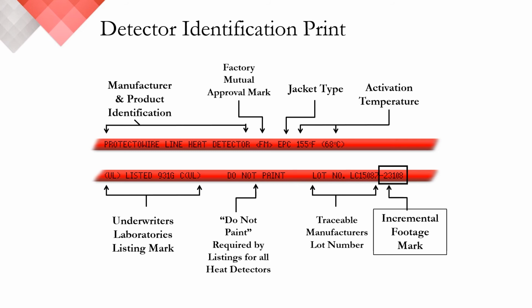So we recommend recording the length of each zone during the initial commissioning process, as that can be very helpful later when troubleshooting. Further, certain Protectowire control equipment is available with an alarm point location meter. This meter will help you determine where the detector is shorted. The short can then be easily located using the incremental distance markings on the outer jacket. Knowing the exact length and location of each zone can also help you to create a facility zone map.